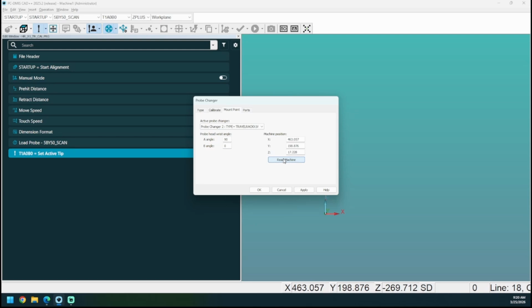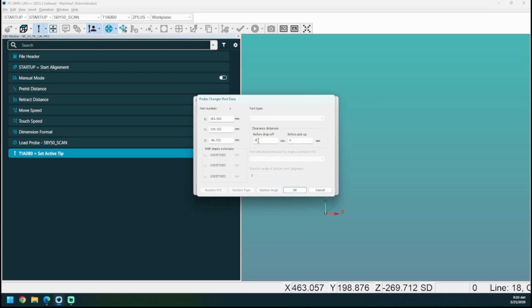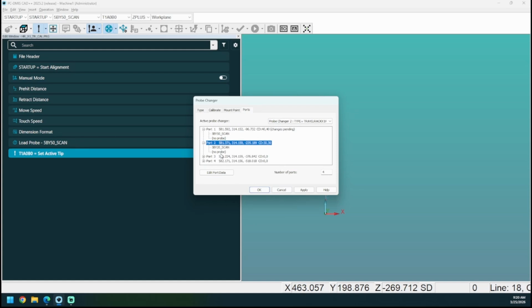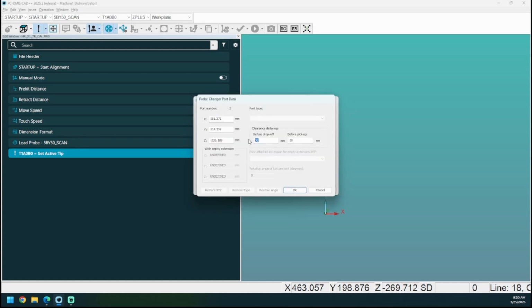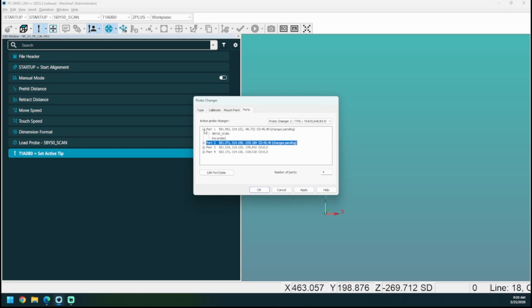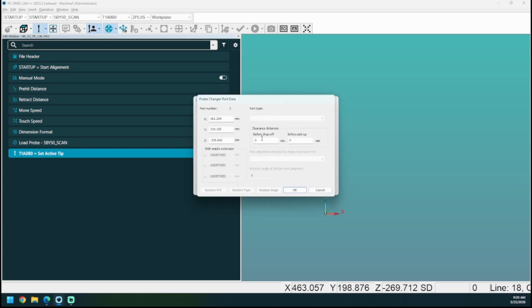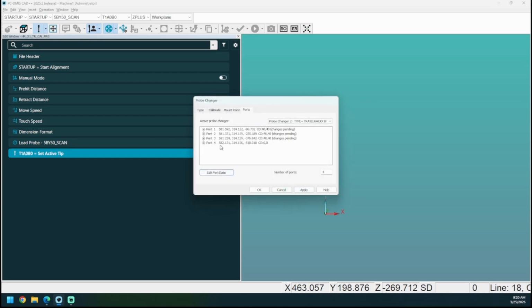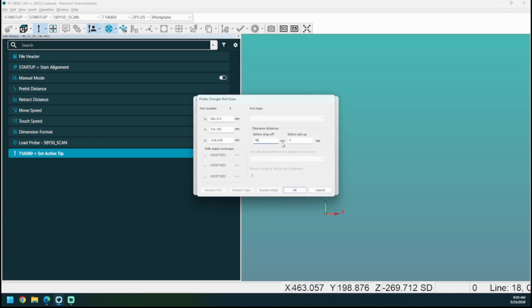I like to have my probe go to the left of the travel rack, ensuring there's enough space between the probe and the travel rack for a wrist rotation. And then we're going to go to the ports tab. This is where I'm going to change the clearance distance. You need to change it to 40 millimeters before and after pickup for all of the ports, and then I hit apply. Then we're going to go back to the Calibrate tab.